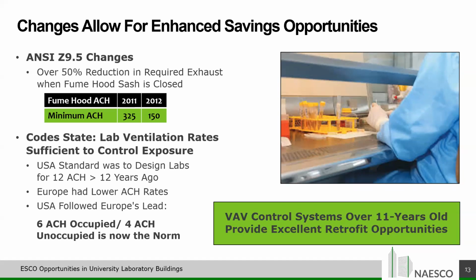Finally, with the cost of energy being what it is, and seeing the energy bills and what hogs these buildings were, the US followed their lead, and it became an acceptable design practice to have 6 air changes per hour in the lab when the lab is occupied, and 4 air changes per hour when the lab is unoccupied. And that was a big shift. So if you've got labs, even if they have an existing VAV control system in them, and they're over 10, 11 years old, chances are there's great opportunity to go in there and retrofit those with new controls and get your new air change rates. And it is a common and accepted practice to use occupancy sensors to do real-time unoccupied, occupied scheduling. So you're not just doing time of day scheduling, and there's significant energy savings to be had.